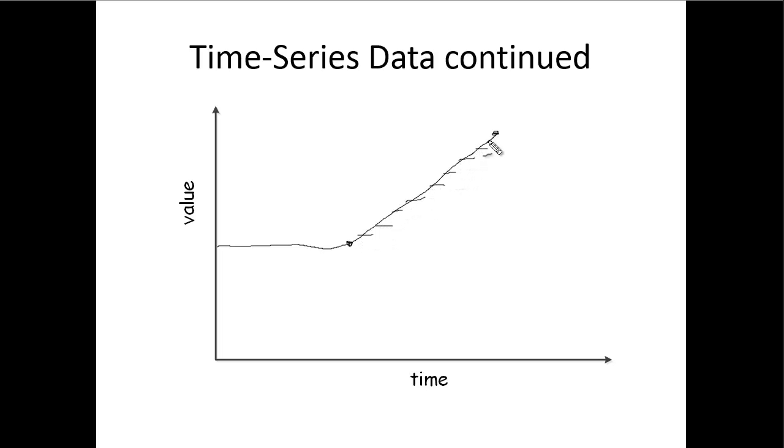And so, even though it's not a very interesting signal, I'm using up a bunch of my space again. I'm using up a bunch of storage space, and then that's going to affect my performance when I go to look at the historical data. And so really what I want is an algorithm that will take less data on any kind of a linear signal, right? And then take more data when it's not really all that linear.